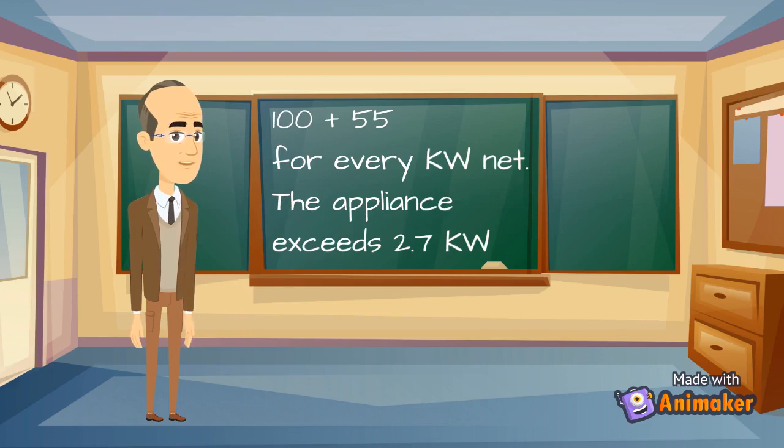We now need to calculate the vent to suit the appliance. First, let's take a look at the formula. No matter what the kilowatt input is for a flueless space heater in a room, we start with 100 centimeters squared of permanent vent size.